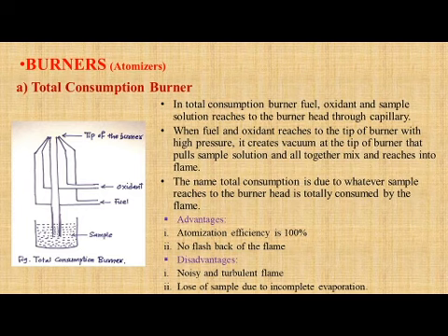It has some disadvantages. It gives a noisy and turbulent flame, which means the flame has noise. We'll get somewhat bigger noise in the flame. Then there is loss of sample due to incomplete evaporation. Sometimes there is a loss of sample due to incomplete evaporation.